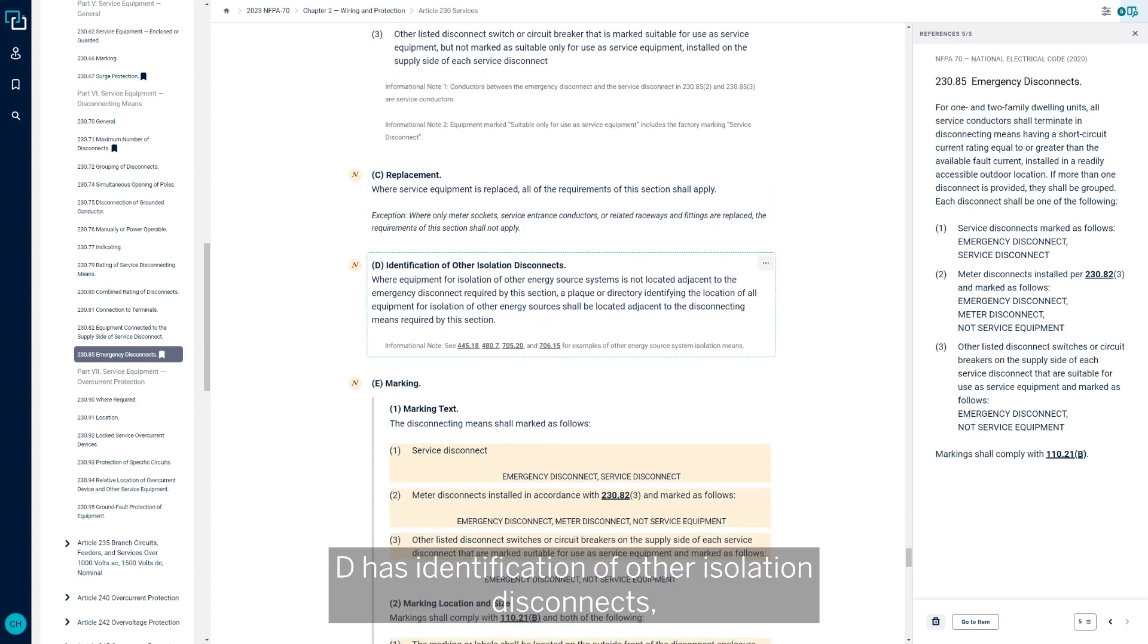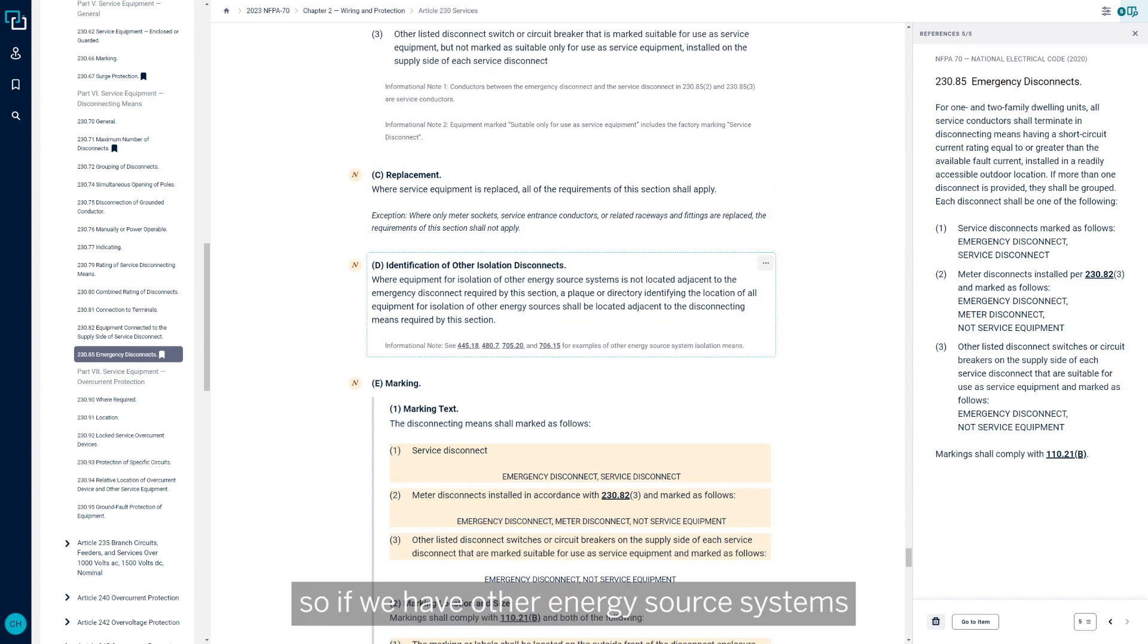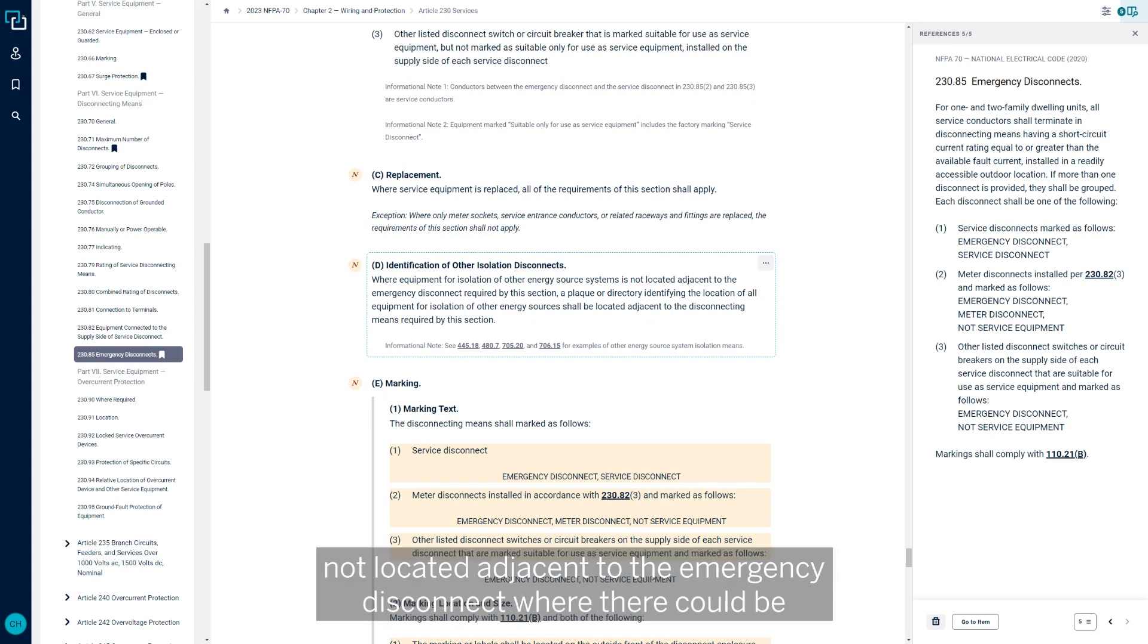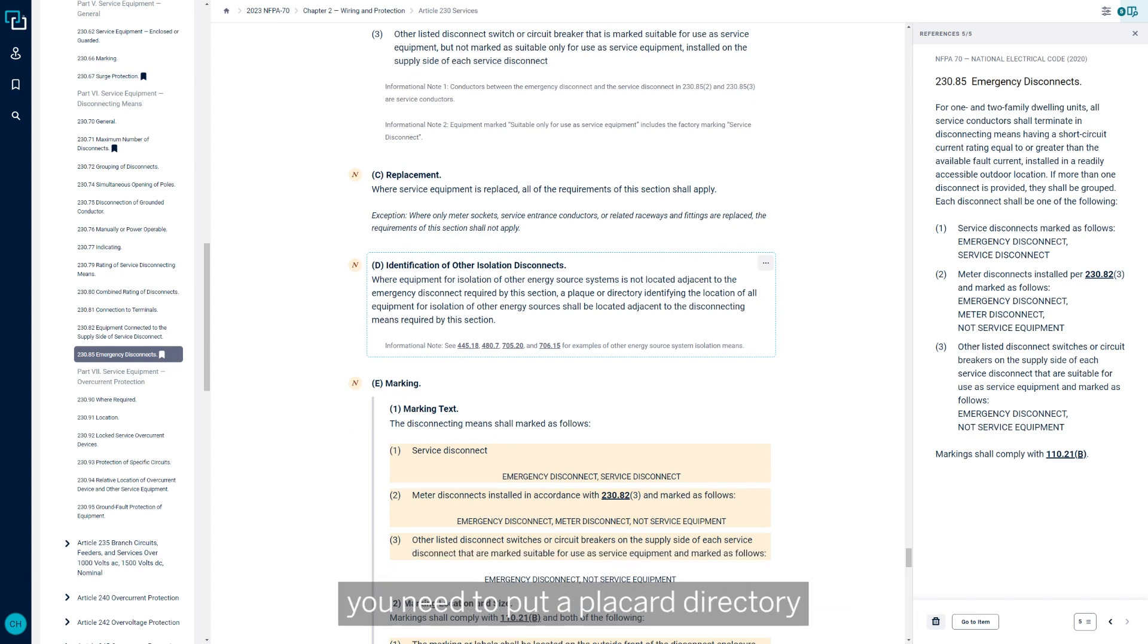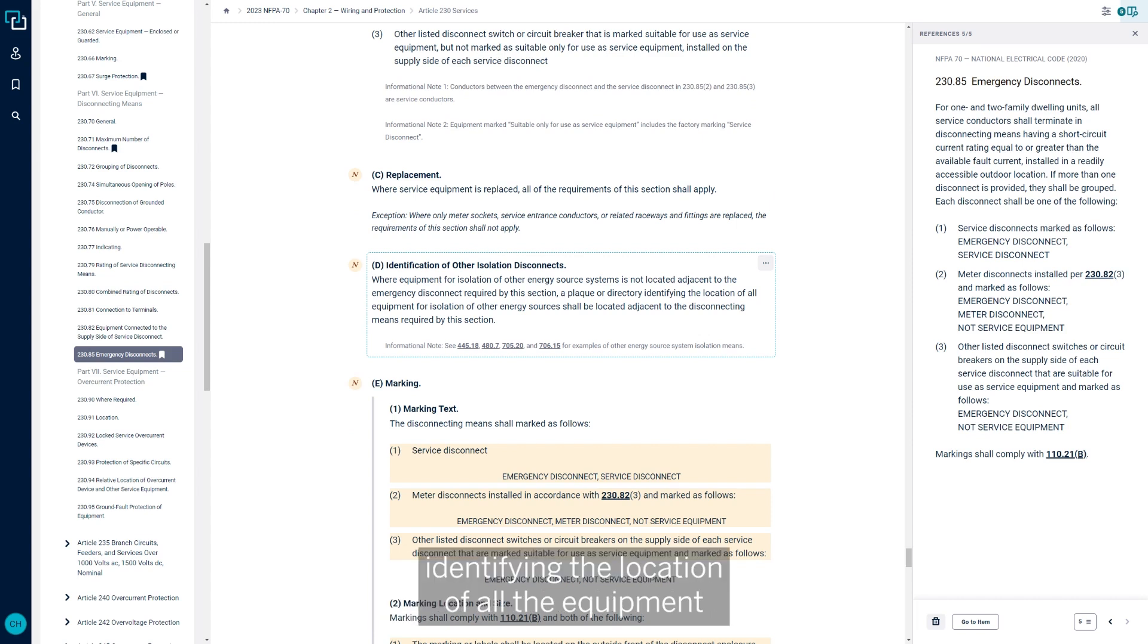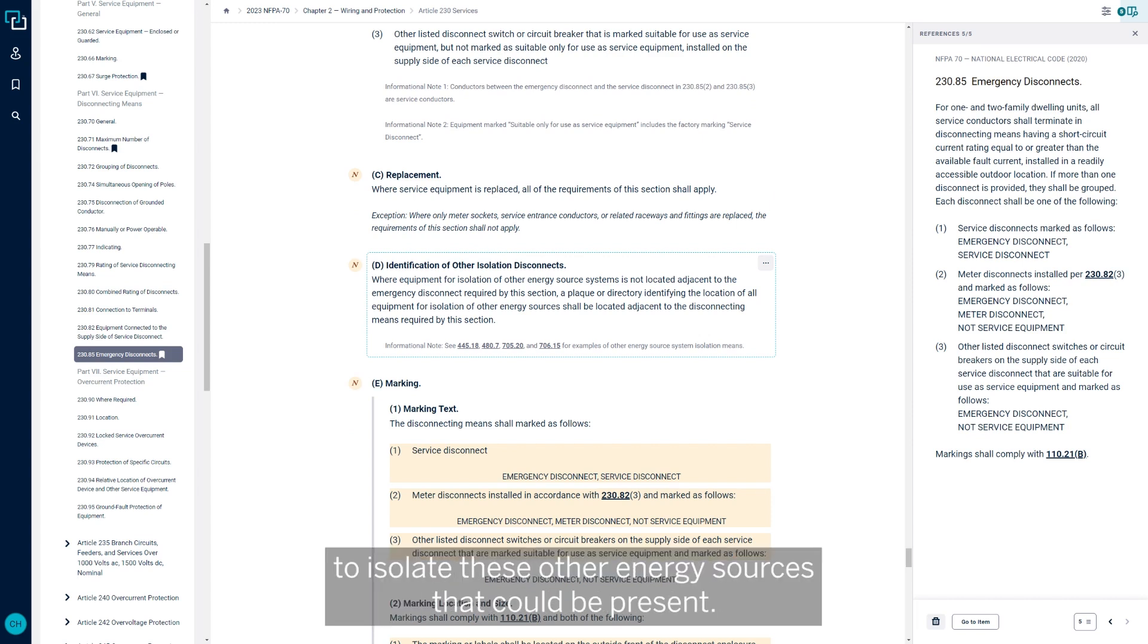Part D has identification of other isolation disconnects. If we have other energy source systems not located adjacent to the emergency disconnect where there could be some other means, maybe solar that's feeding power to the home, you need to put a plaque or directory identifying the location of all the equipment to isolate these other energy sources that could be present.